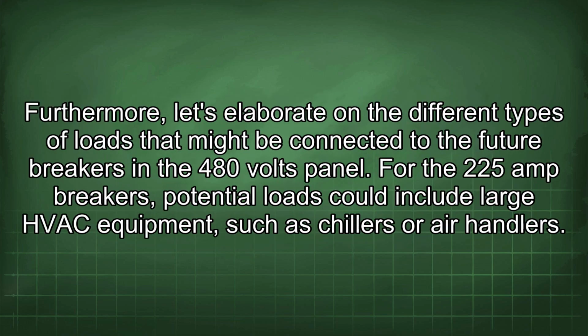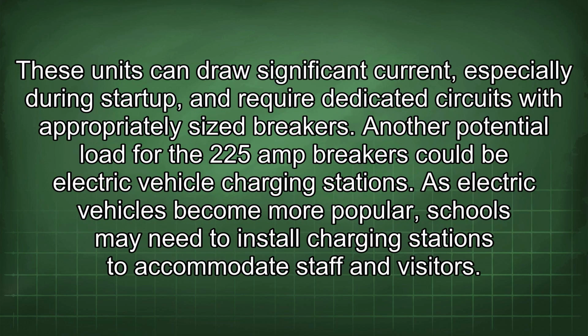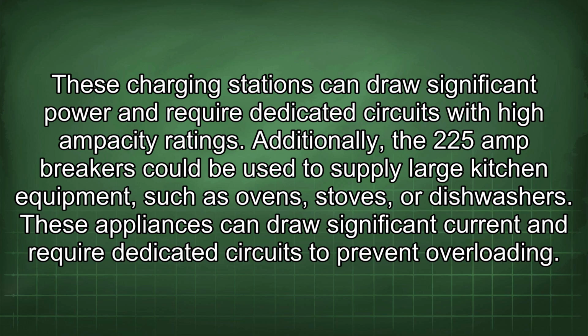rated capacity. Furthermore, let's elaborate on the different types of loads that might be connected to the future breakers in the 480 volts panel. For the 225 amp breakers, potential loads could include large HVAC equipment, such as chillers or air handlers. These units can draw significant current, especially during startup, and require dedicated circuits with appropriately sized breakers. Another potential load for the 225 amp breakers could be electric vehicle charging stations. As electric vehicles become more popular, schools may need to install charging stations to accommodate staff and visitors. These charging stations can draw significant power and require dedicated circuits with high ampacity ratings.